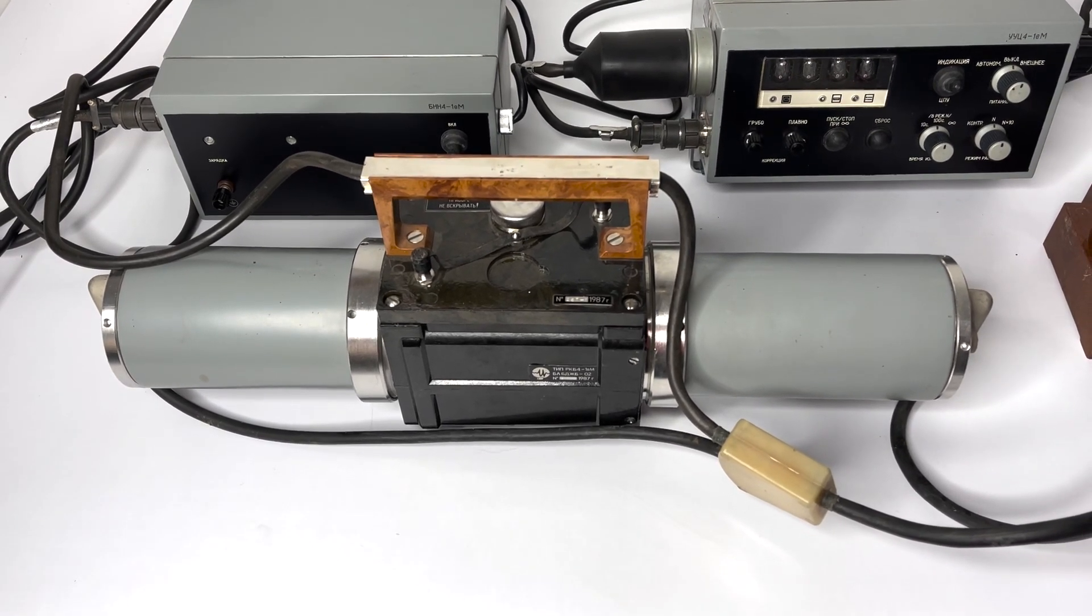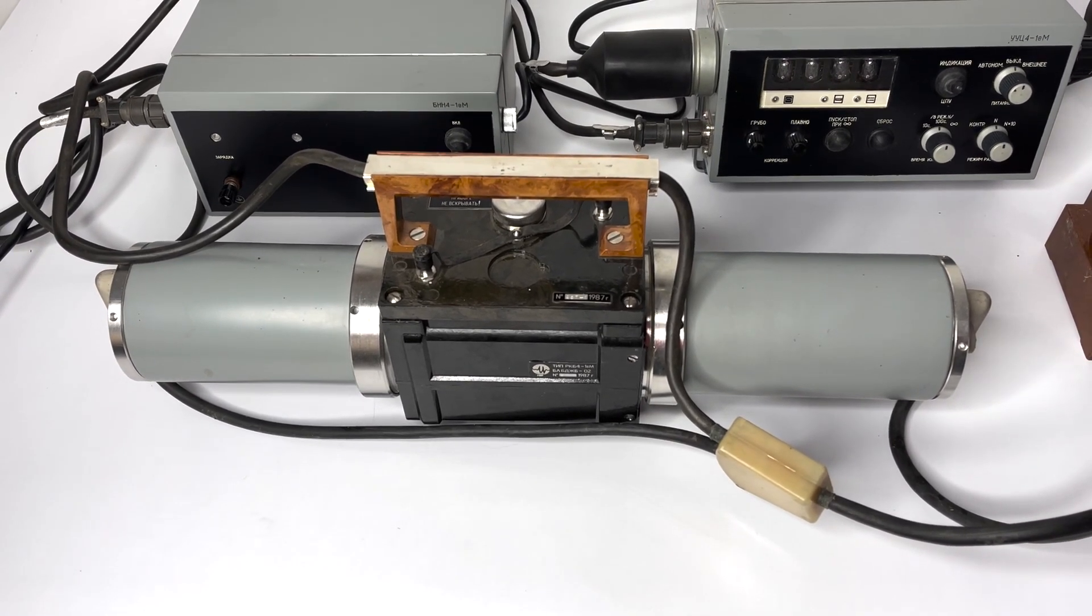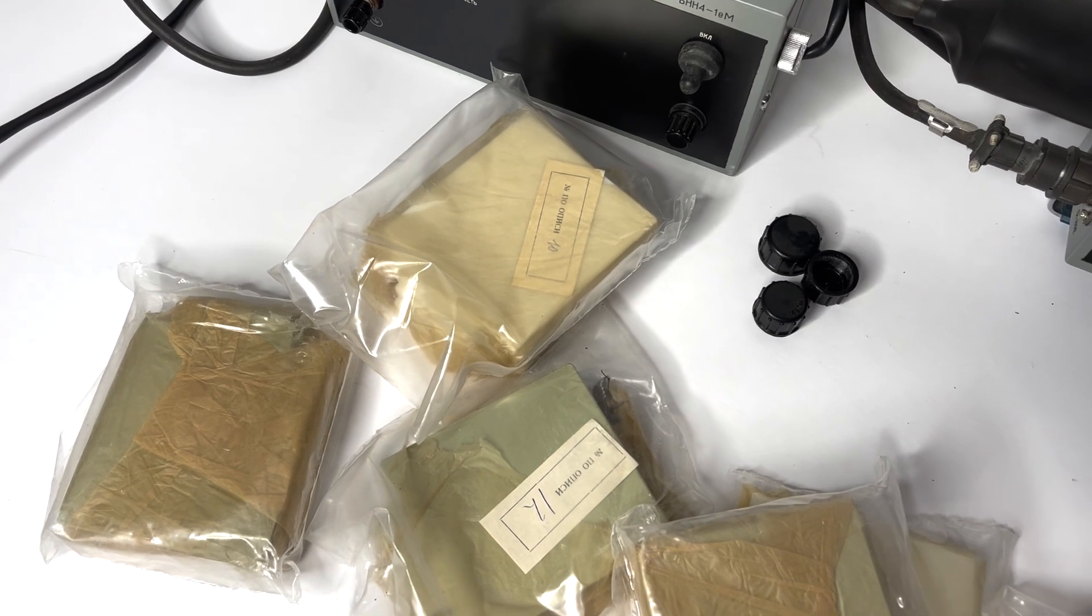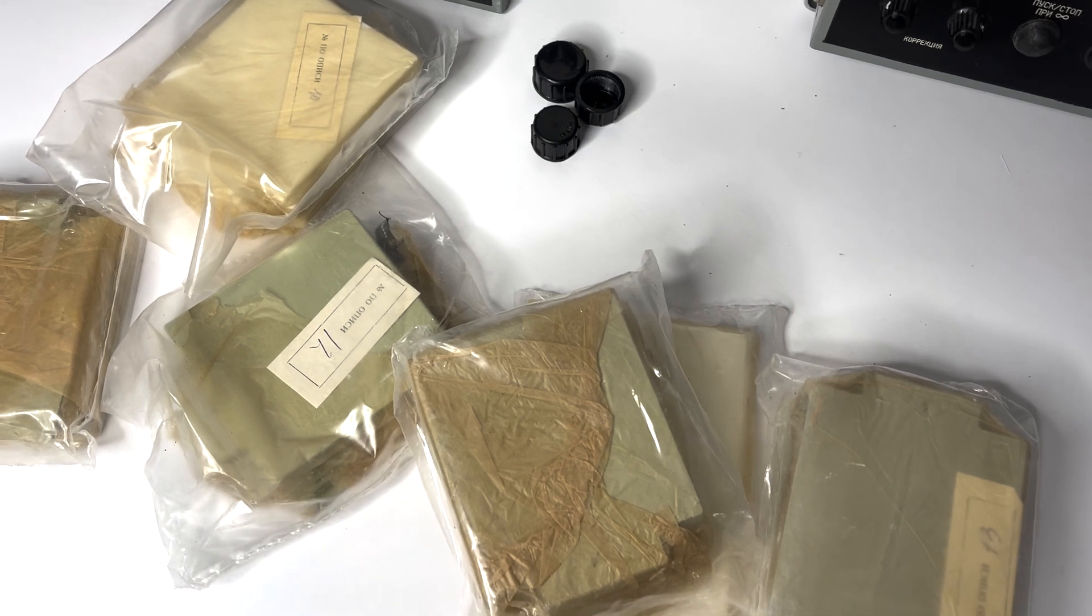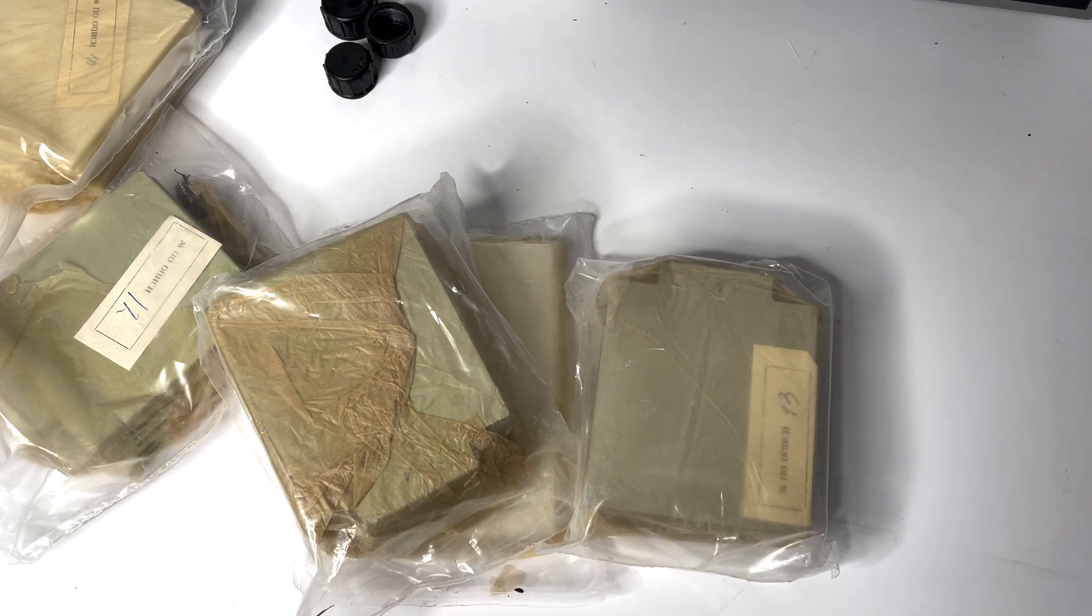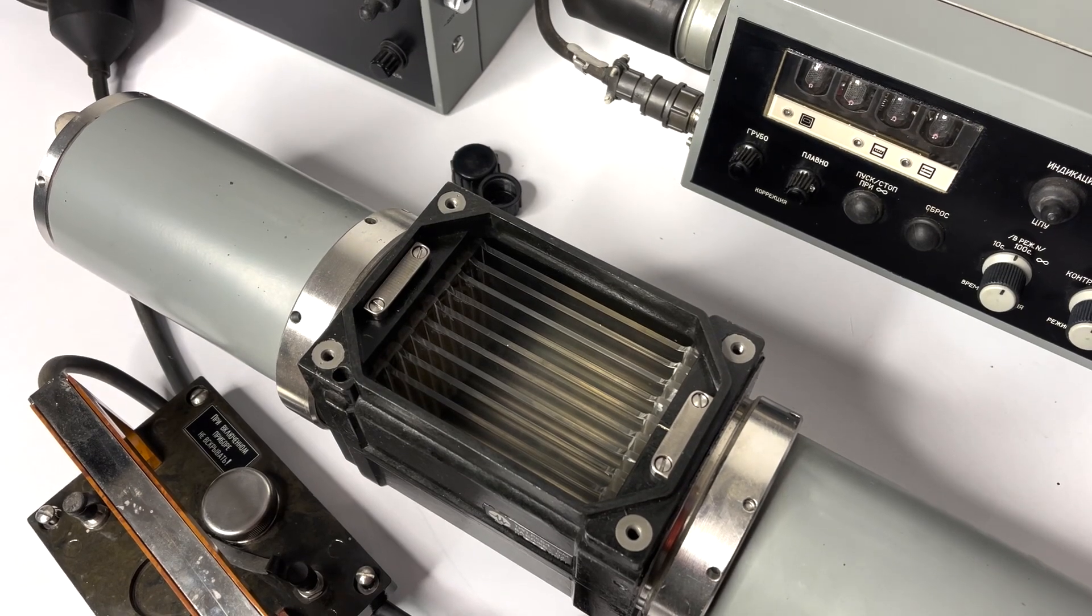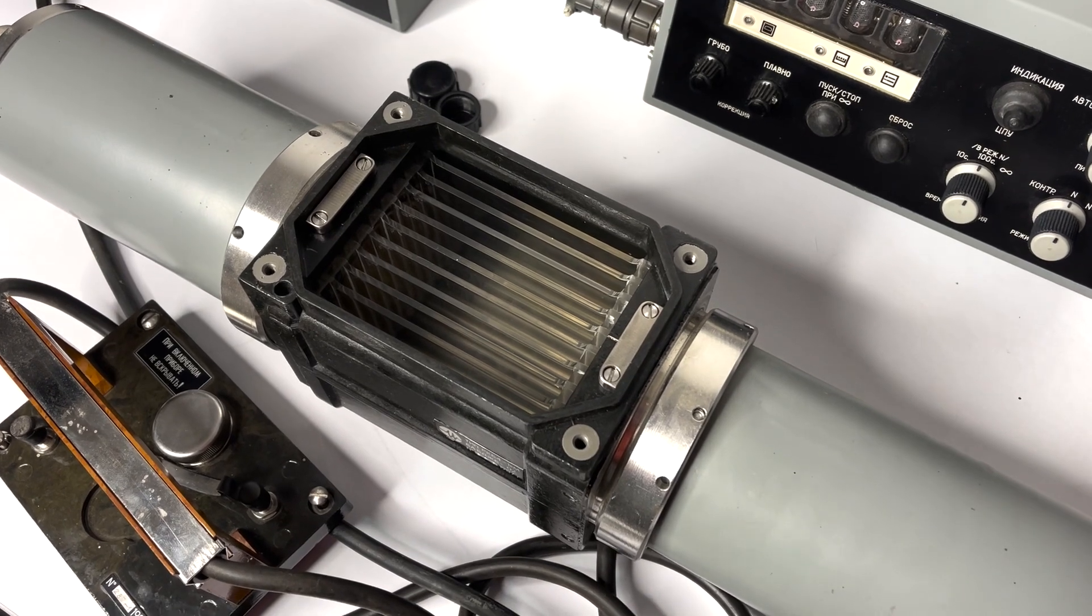This detector requires certain adjustments if you work not with water, but some liquids with higher density, such as milk, for instance. So for this you may need so-called phantoms, that's the same panels, but from metal or different material. So you install them instead of some of the insulation panels. It's very well explained in the manuals, because some of them are also designed for calibration, and according to the user manual, this calibration has to be done practically every time before you actually make any big measurements.